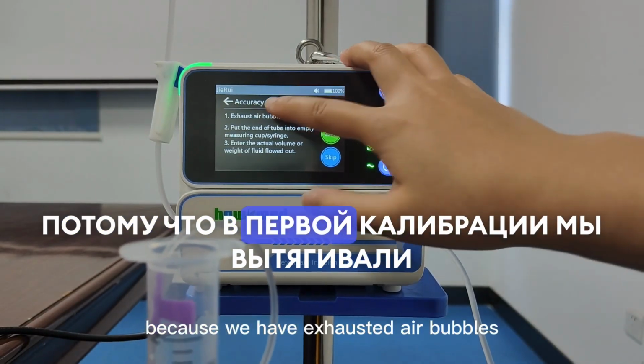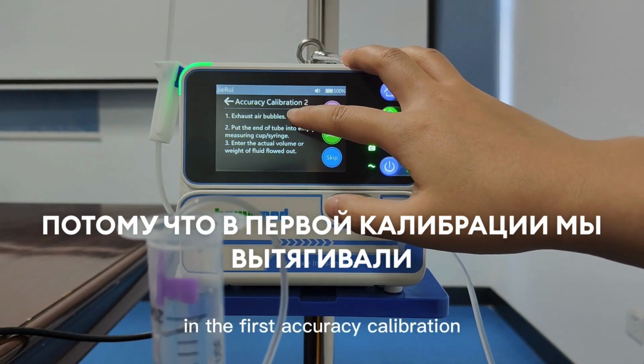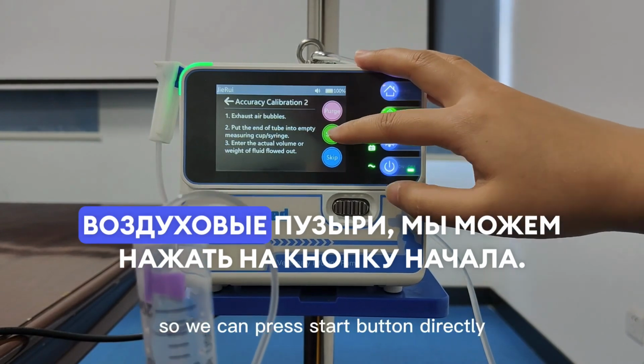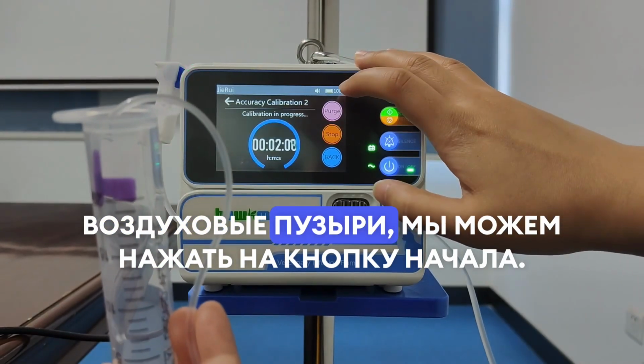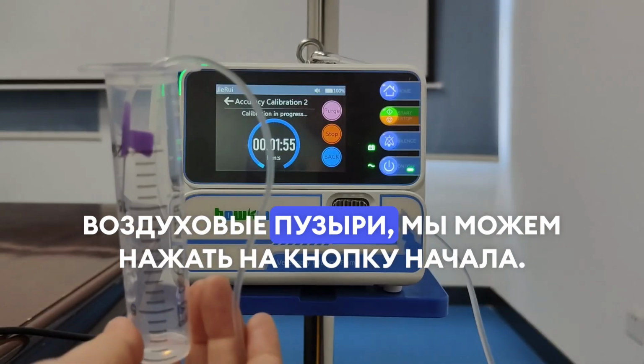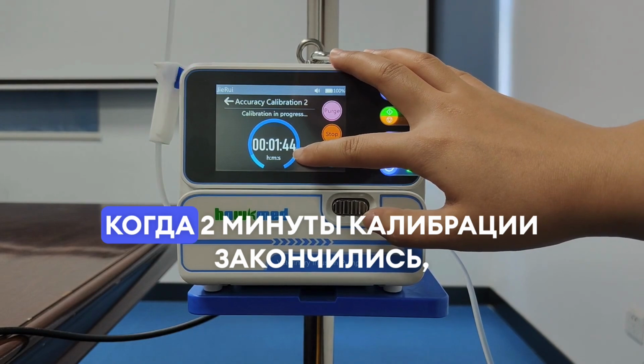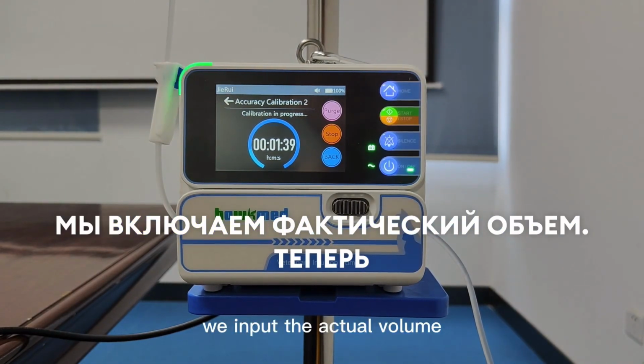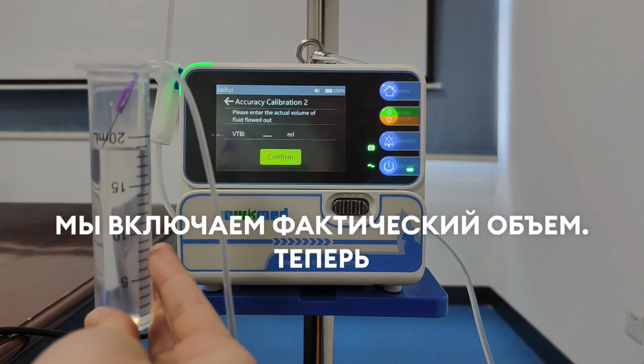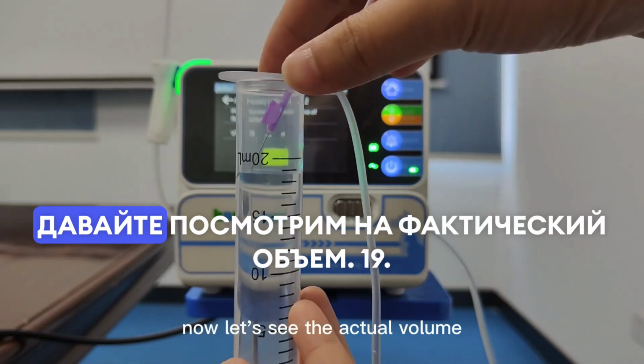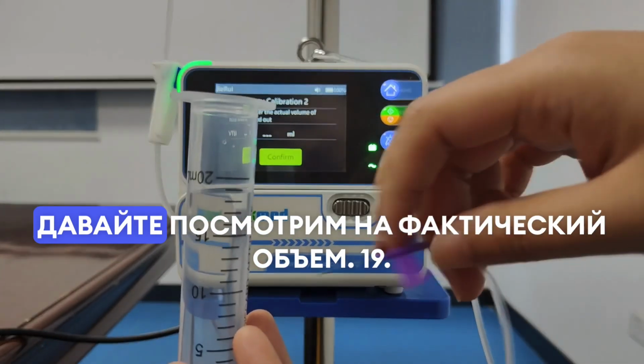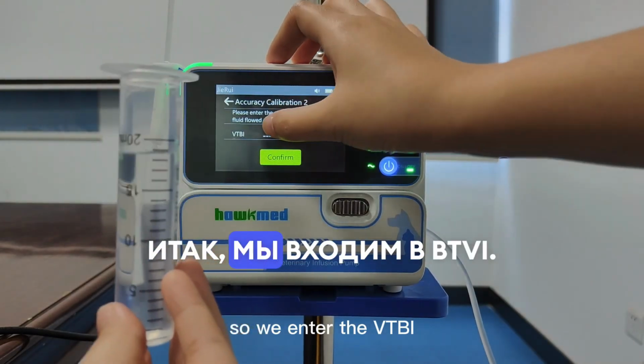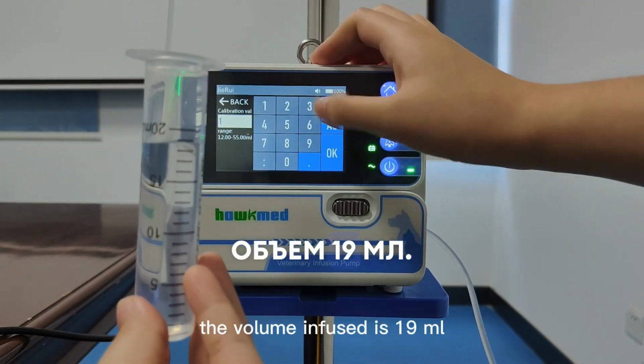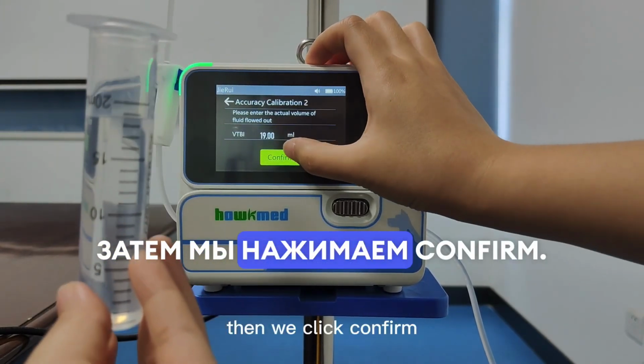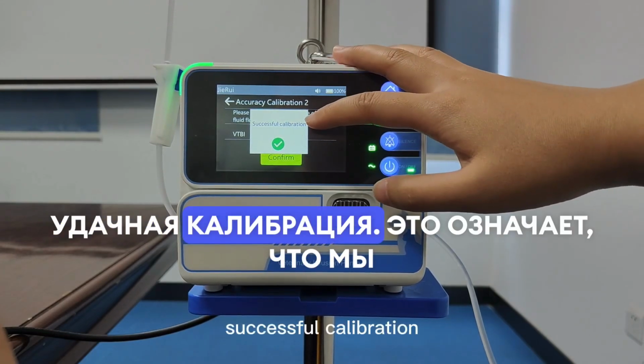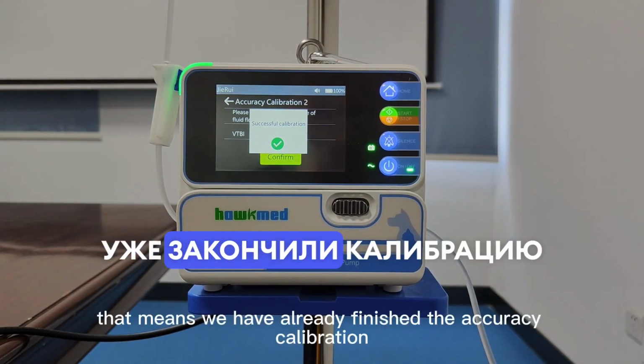Because we have exhausted the air bubbles in the first accuracy calibration, we can press the start button directly. When the 2 minute countdown is over, we input the actual volume. Now let's see the actual volume. 19. So we enter the VTBI. The volume infused is 19 milliliters. Then we click confirm. Successful calibration. That means we have already finished the accuracy calibration.